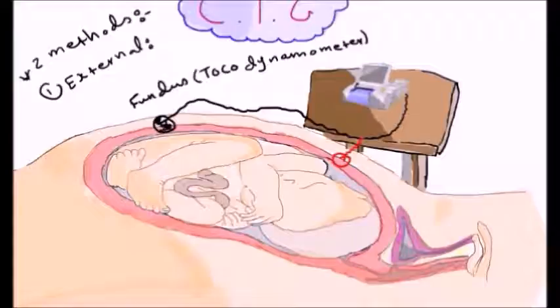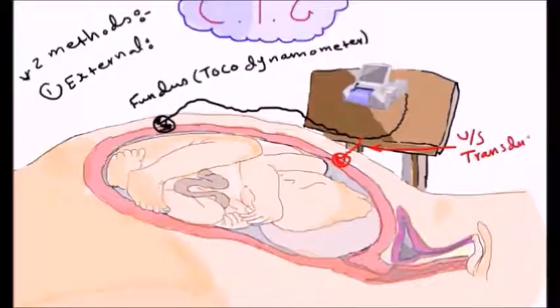So this is our fetus and our device. Now let's apply our electrodes. There are two methods for applying the electrodes. The first is external CTG, which is usually used. Here we apply one electrode on the abdomen facing the fundus for measuring the uterine contractions — this is called the TOCO dynamometer. We have another electrode applied in the area between the umbilicus and the right iliac fossa for measuring the fetal heart rate, which is an ultrasound transducer. On the computerized display, upward is the fetal heart rate and downward the uterine contractions.